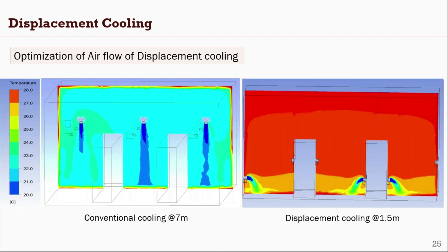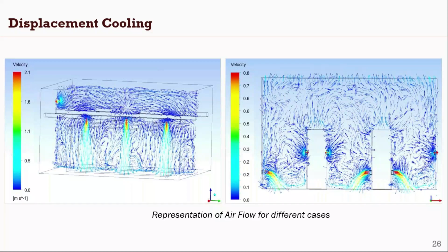It has been found that if 1 meter per second velocity flows through the displacement cooling, the occupant will feel draft. I'm not showing all the results here, but you can see from the video that with the supply duct at 7 meters, the standard velocity is 2 meters per second.